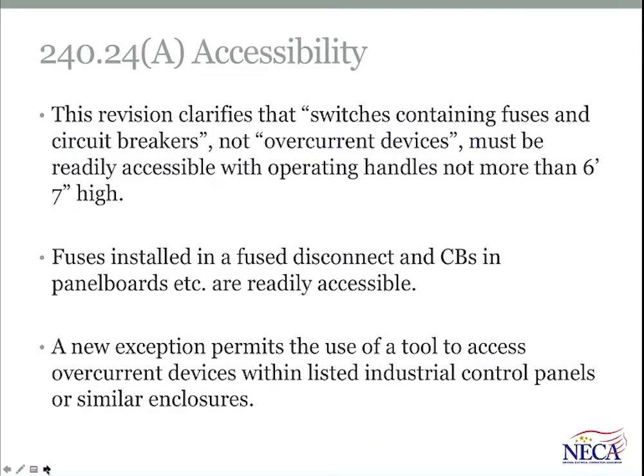Panel 10 has responsibility for overcurrent protection, dealing with fuses and circuit breakers, and Section 240.24A deals with accessibility of those overcurrent devices. There's a revision here that clarifies that the switches containing the fuses and circuit breakers, not just the overcurrent devices, must be readily accessible with the operating handles not more than 6'7" high. Prior to this revision, it was just the overcurrent devices themselves, when it's actually clarifying the operational handle of the switches we're dealing with, and not the overcurrent device.